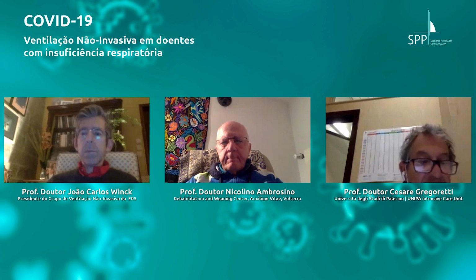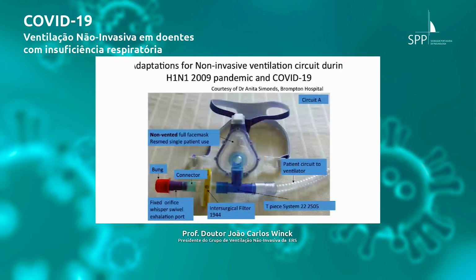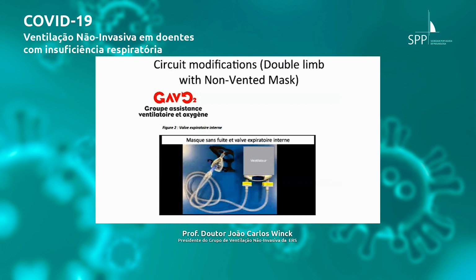So remember another important point. Can you switch back to the former slides? Okay. If you use a ventilator that does not have a blender, like the Evo or the V60 or the V40, the problem is how to increase the FiO2 in this system. It's not easy, almost impossible, because you need a large amount of flow, up to, I guess, 40 liters per minute inside the ventilator. I didn't do any kind of measurement, but I guess that all depends on patient flow. If the patient is doing 1 liter per second of flow, that means 60 liters. To obtain 100% oxygen, you need 60 liters per minute of oxygen.